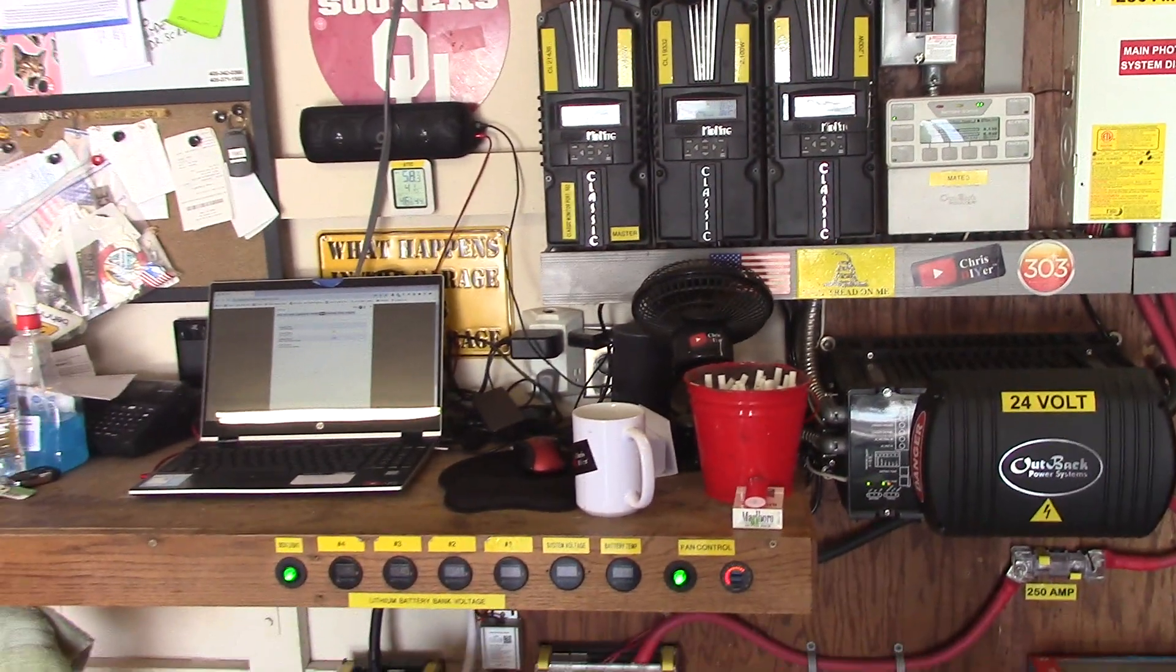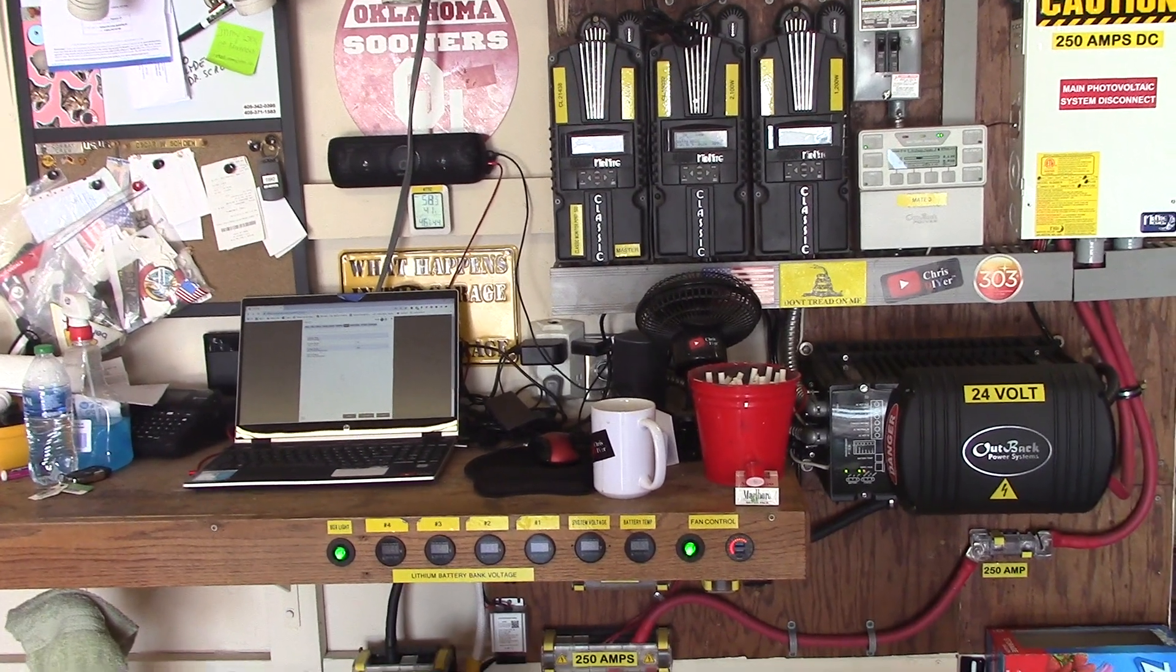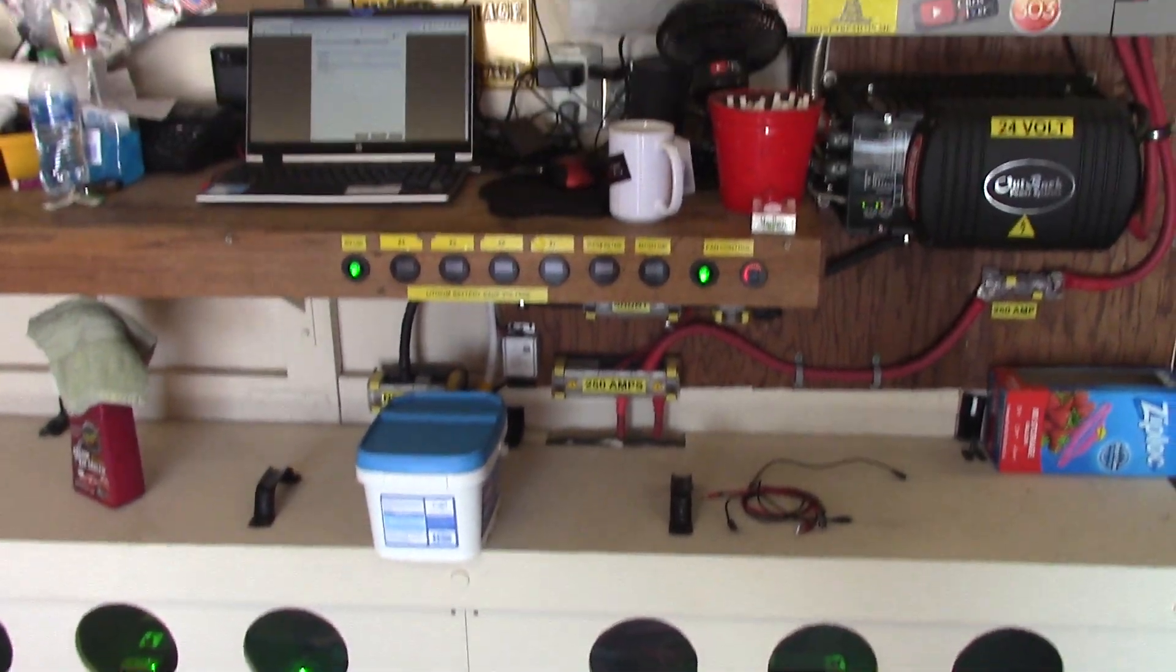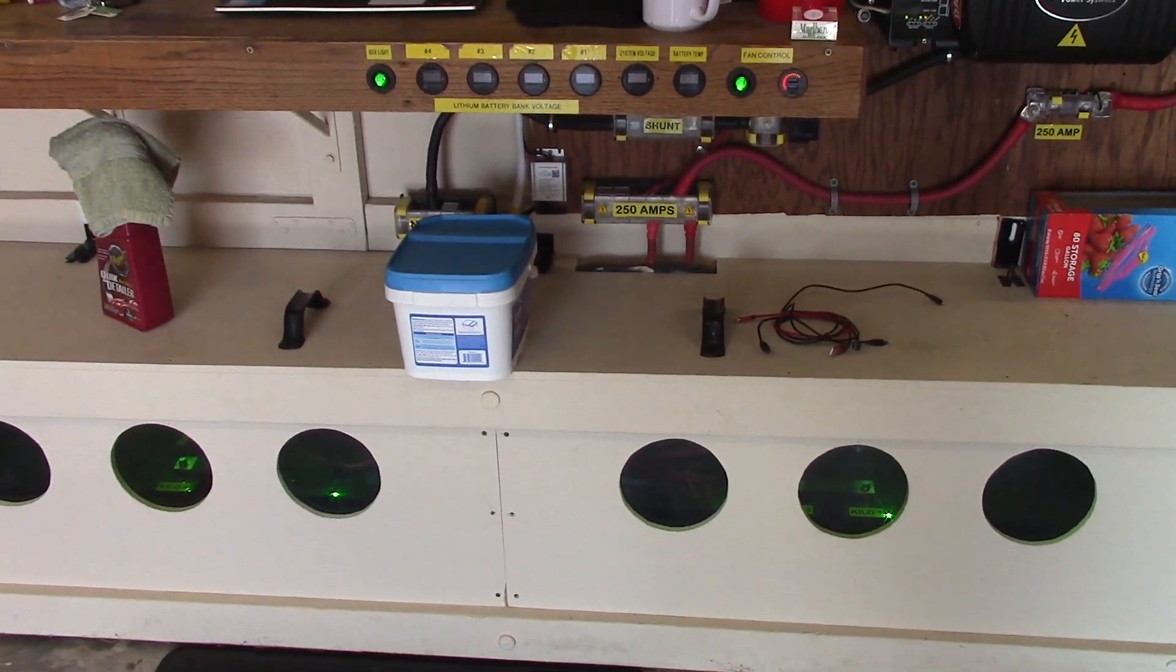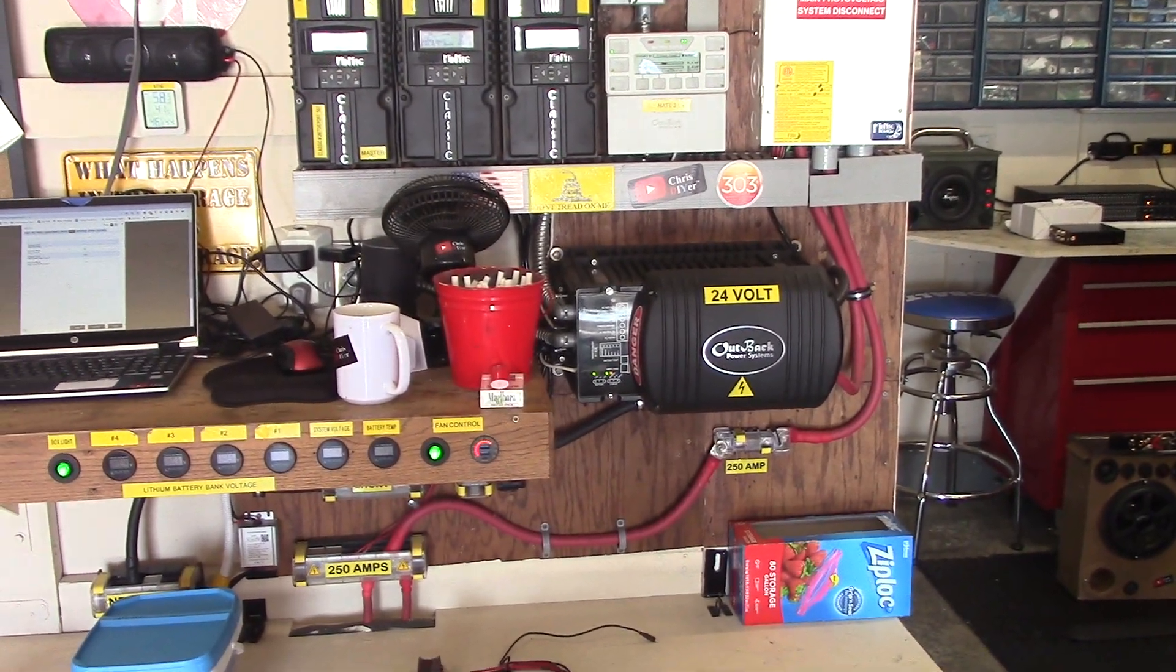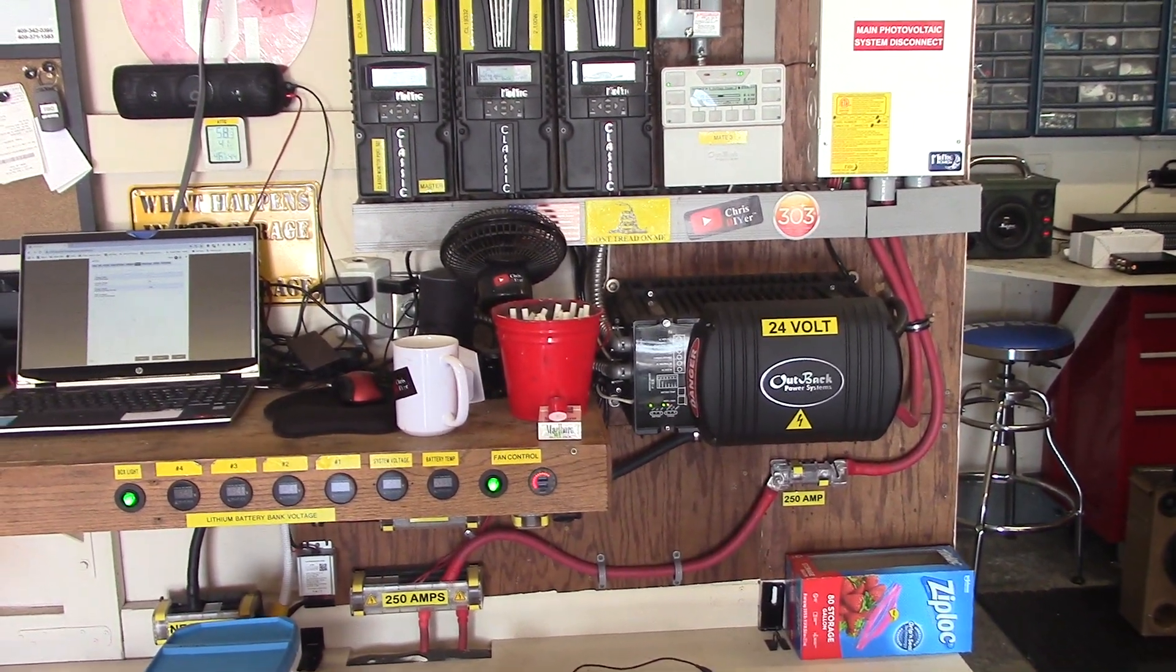So now essentially this thing is going to be autonomous. If I've got sun to charge, it'll charge and invert all day to the batteries. If I don't have sun, keep everything connected. And then when the battery voltage goes down to 26 volts, the charger right here will kick on. It'll go up to 28 and give a full charge, and then invert.